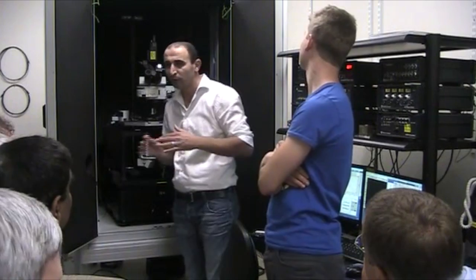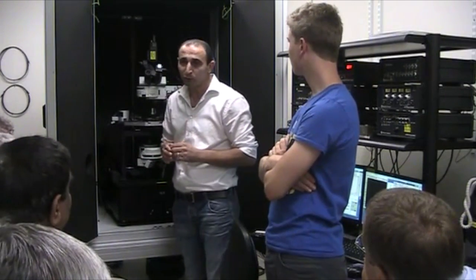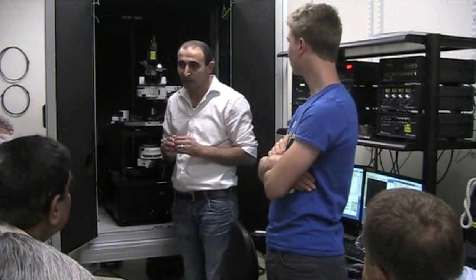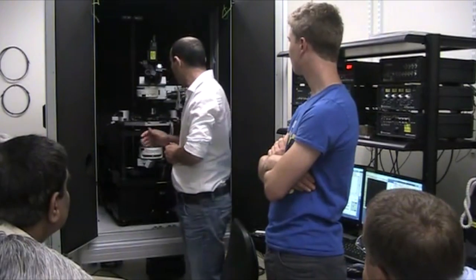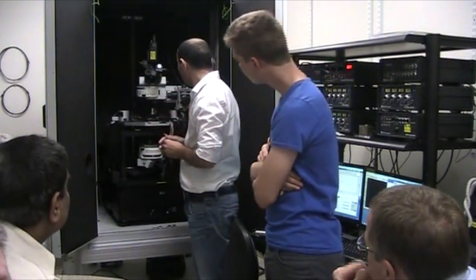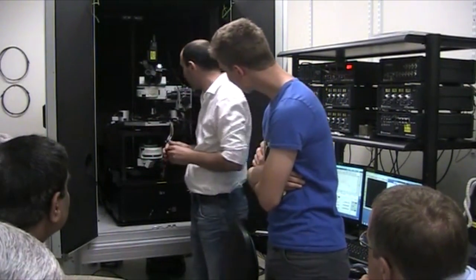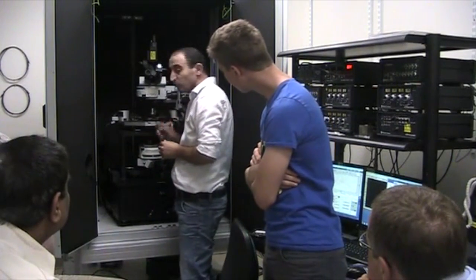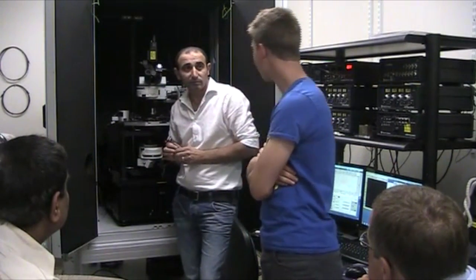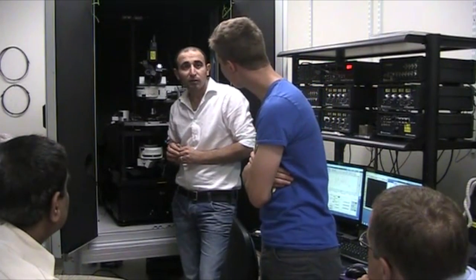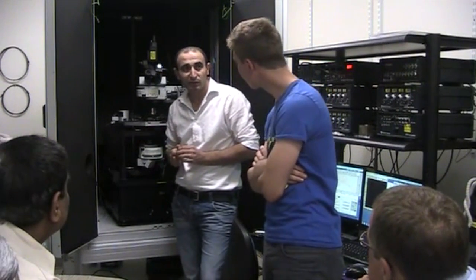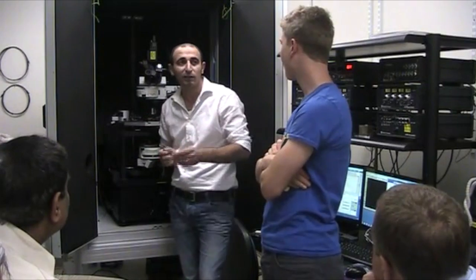Normally, most AFM systems use between 5 to 20 microns. So this is good for rough surfaces, for cells, for fibers, like textile fibers, or wood fibers, plastic fibers. That would be good to cover with AFM, such roughnesses. So the AFM with the laser deflection, where is the laser? There is no laser deflection here. It's using the tuning fork for the feedback.